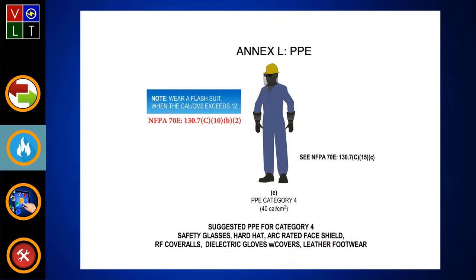And one other thing that I would point out, on most construction sites, the guys that really work in panel boards and get into where there's energized components, maybe at 240, 120, they're trained to do that, but the other guys are only trained to do the wiring, run the conduit, the cable, set the boxes and stuff like that. And they're not allowed to go into the room where the panel board is that contains the circuitry that gives them the temporary power that they need in accordance with Article 590 of the NEC. So kind of keep that in mind.